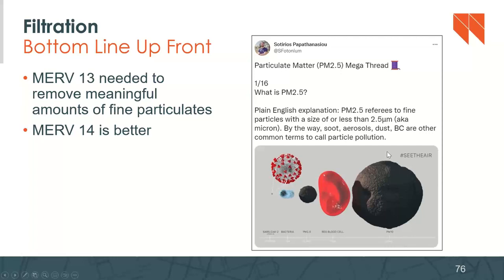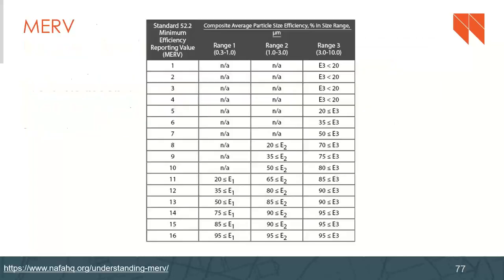Here's an example, taking COVID, for example, right? The size of that particle compared to an individual bacteria, compared to your red blood cell, and then these are particulate matter that are 2.5 microns, and then this is a particulate matter that is 10 microns. And so you can see that the very small COVID virus particle is way smaller than even these very small things. And so a MERV 13 rating for a filter is kind of needed. You can see down here, in terms of the particle size efficiency, these MERV 13s and MERV 14s are needed to capture these pretty small size particles.